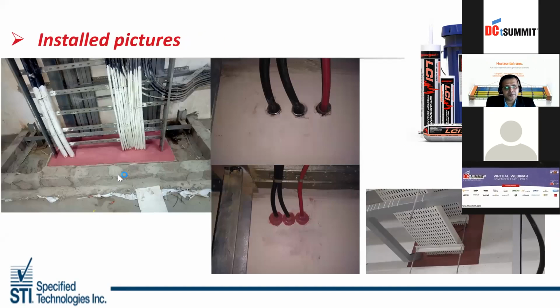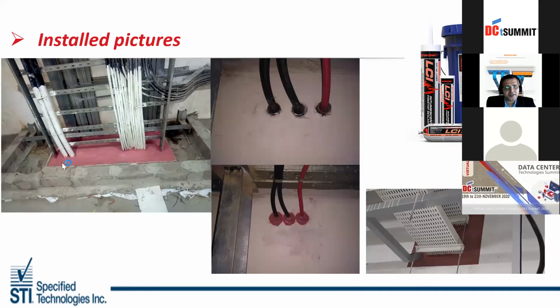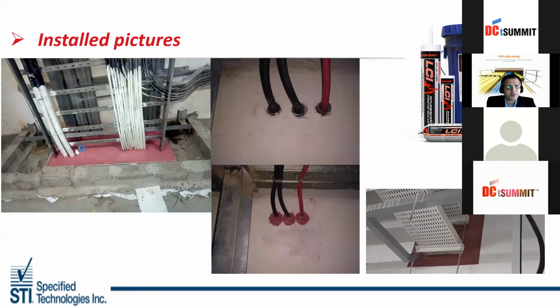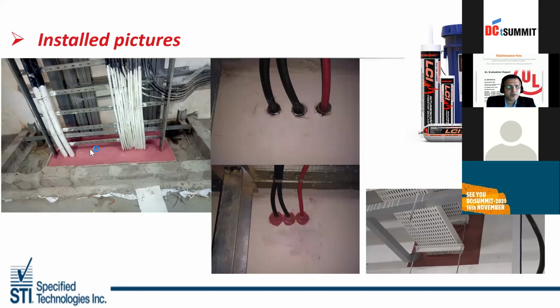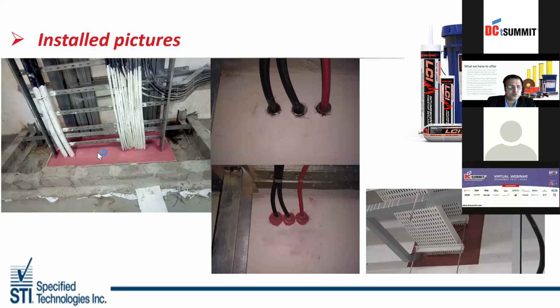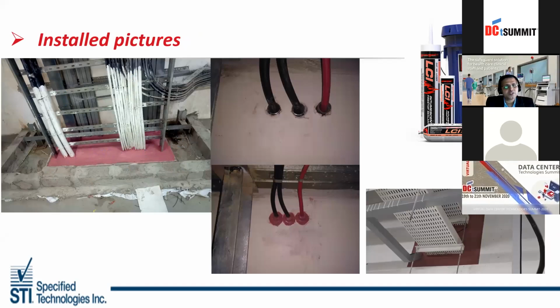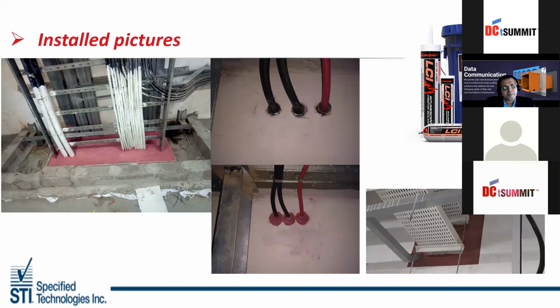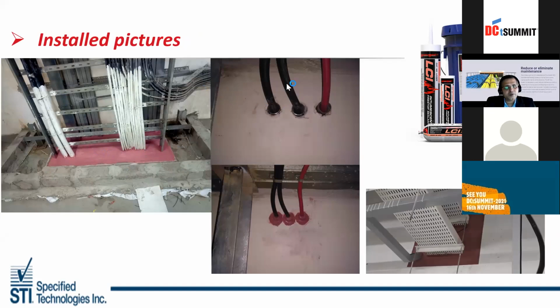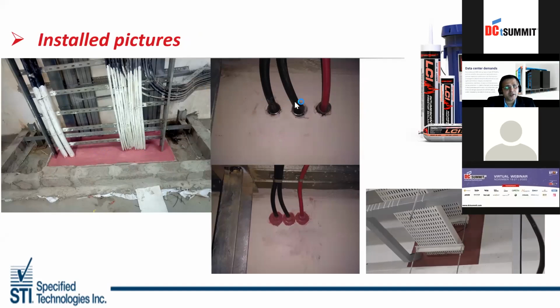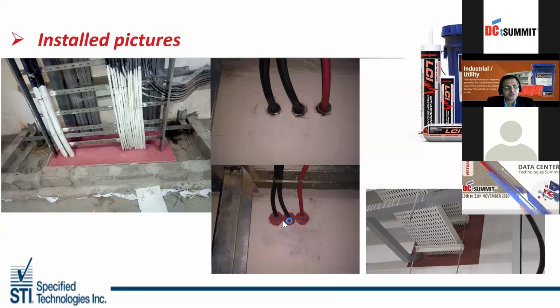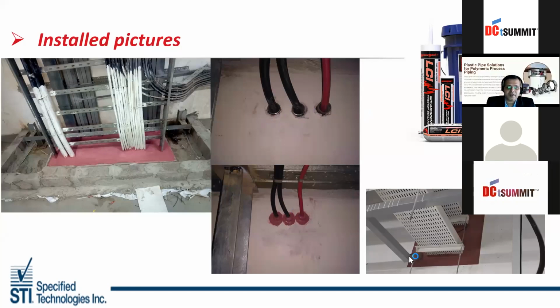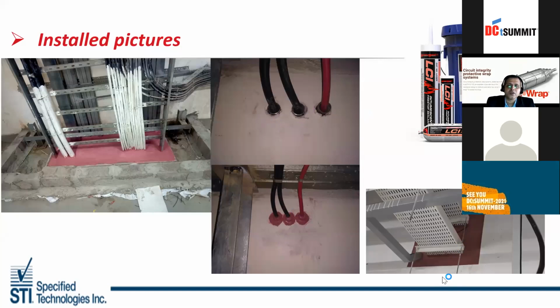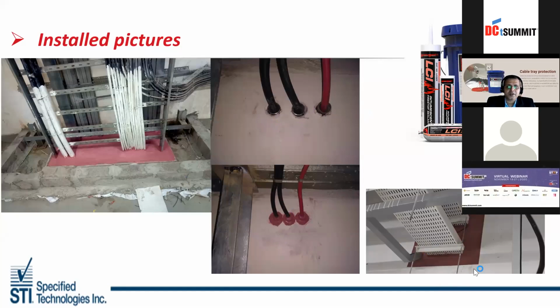Here I'm trying to show you some install pictures. Towards your left-hand side it is a floor, and there are a couple of cables and cable trays passing through the floor. The pale pink in color is the intumescent sealant which is used, and the white part you're seeing is the cable coating, which is used for reducing the speed of fire. The cable coat reduces the speed of the fire. Okay, in the center you have a gypsum board, and you can see a conduit and a single cable passing through. So again, you can see how it is fire sealed. And towards your right-hand side bottom is a multiple cable tray passing through a wall. So in all these three scenarios, the same intumescent product is used.